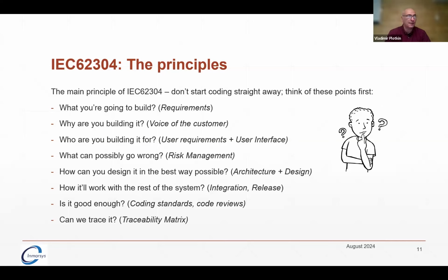How are you going to be planning your coding activities? So coding standard, how are you going to be doing your code reviews? What kind of tools are you going to be using? So, for example, some of the companies prefer to use pre-validated tools, like certain compilers which come with the functional safety certificate. Some other companies prefer to pay less because these certificates are really expensive, and they buy cheaper tools or go with the free tools, and then validate the tools themselves, basically spending money on test activities and the requirements activities for those tools.